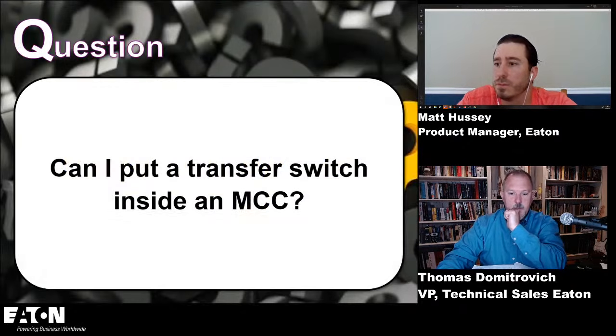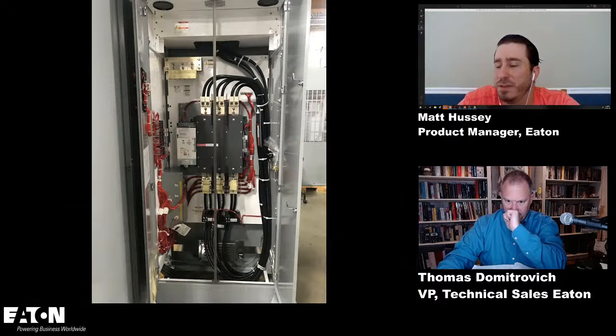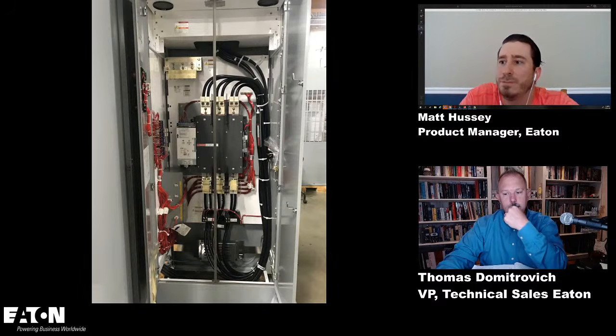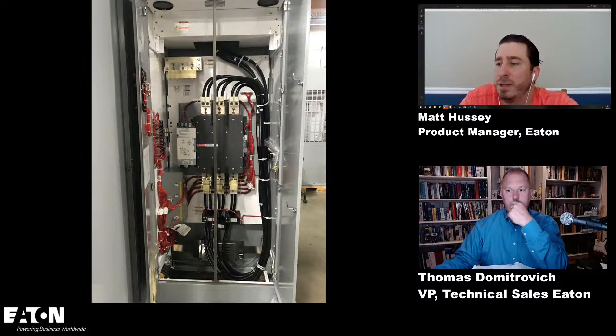Can you put a transfer switch inside an MCC? Of course you can. You could do some things like this where it might just be a main incoming for normal and an emergency supply. This one actually might be one, Tom, where even the bus is split, where under normal operation an entire lineup is fed for typical use, but then if it's an emergency supply, it's transferred over, maybe only parts of the lineup are fed.